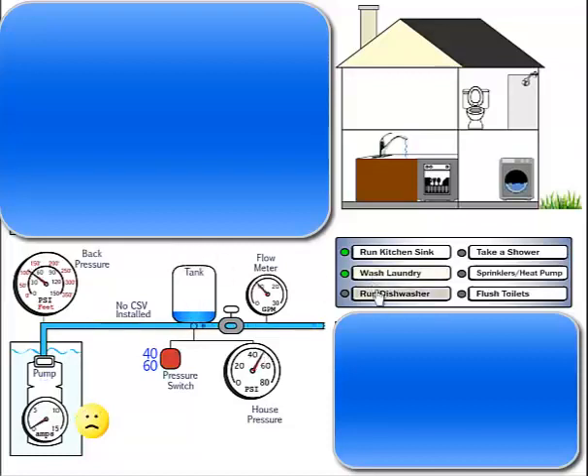The only way to keep a 25 gallon a minute pump from cycling is to always use 25 gallons a minute or nothing at all. But as in this case, even with every tap in the house open, the most this system can use is 24 gallons per minute. So any water outlet or combination of water outlets will still cause the pump to cycle on and off.